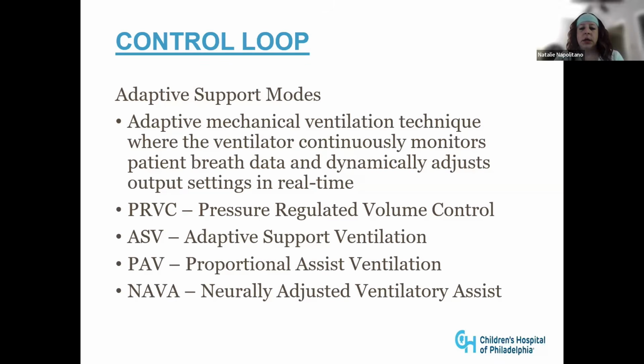Proportional assist adjusts pressure proportionally to the patient's spontaneous efforts, allowing the patient to dictate the breath size and timing, while the ventilator just assumes a portion of the work, but not all of the work. And then NAVA is a little bit different, neurally adjusted ventilatory assist, and this takes a look at the patient's neural drive. So it takes its cues really from the brain talking to the diaphragm to say, take a breath. When the diaphragm starts to move is when it takes its signal to give a breath. And the extent to which it provides support depends on the force with which the diaphragm contracts.